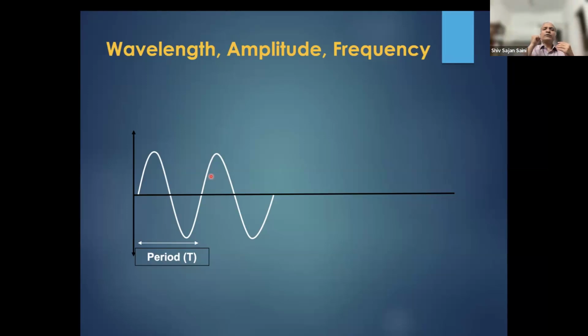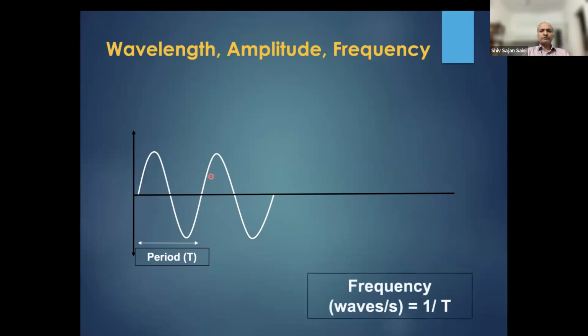Hence, if you use a very high frequency probe to interrogate the deeper structures, we don't see them, because the wavelength is very small. As the waves go inside, there is a lot of loss of signal, and we see all black areas if we use a very high frequency probe to interrogate the deeper structures. So it has to be taken into consideration how deep you want to interrogate. For heart purposes, 5 to 10 megahertz is okay. And as I said, frequency is inversely proportional to wavelength.